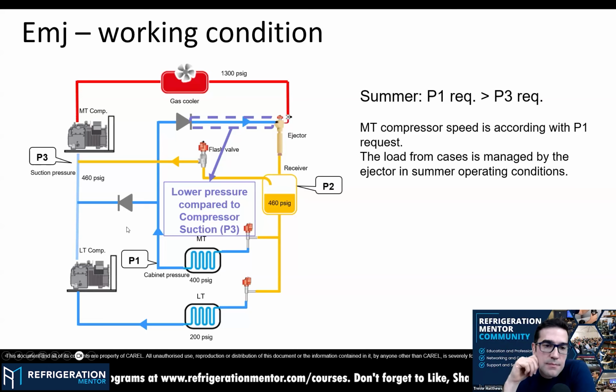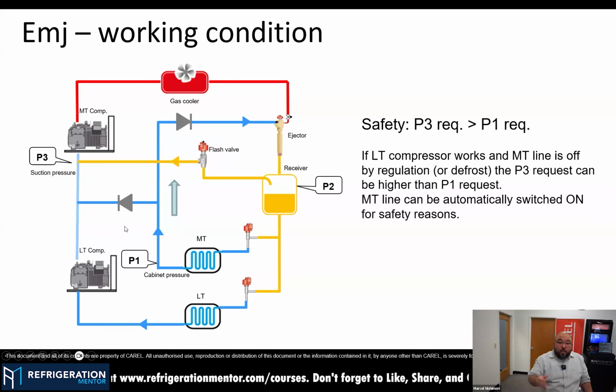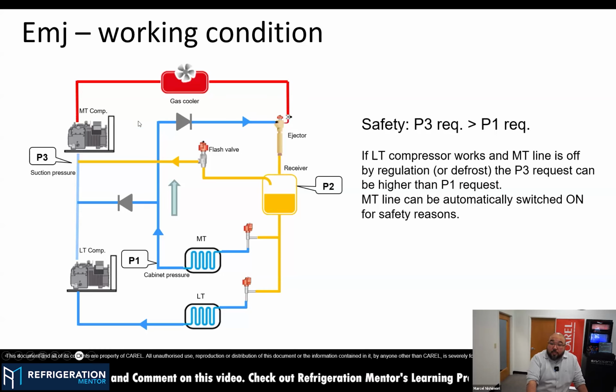Compared to the MT, safety conditions, as I mentioned. If I have all my loads empty in defrost, or any problem with the MT line, and I still need to have my LT line running, I have the P3 probe checking the pressure at that point and making sure that we are maintaining the pressure for the low temp compressors. In this case, P3 will always act as a protection device, with a higher set point to maintain things in the right conditions.